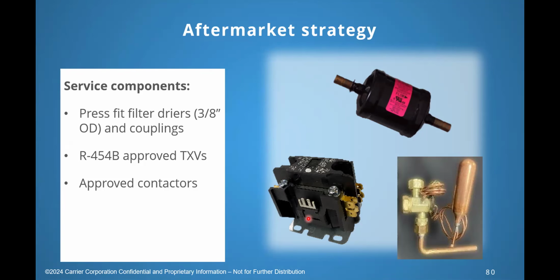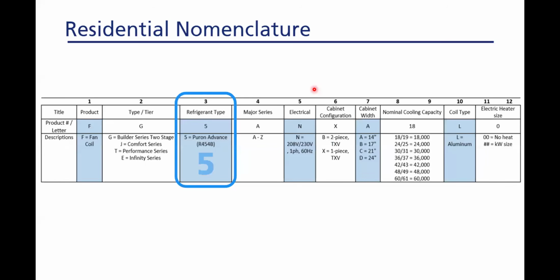You probably don't need to stock a bunch of TXVs because I don't imagine that you stock a bunch of TXVs now. Somewhere in the company we need them, but probably not every location. And the filter dryers, you don't really need to stock the R-454B filter dryers because, as I said earlier, you can use an R-410A one. It's the same media. It's going to have the same rating on it. The only difference is whether it's straight pipe or it's wedge. So you probably can get away with not adding anything in terms of a new part number there.